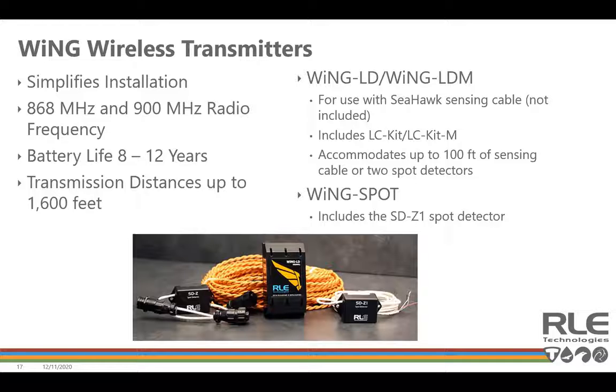The sensors themselves are compact, and they have a battery life of 8 to 12 years, so quite significant. It's a AA 3.6 volt lithium battery that is included with the sensor. Amazing transmission distances, up to 1,600 feet, 600 feet of that direct line of sight from the sensor to the WING Manager controller. And as I mentioned before, the leak detection sensor will accommodate up to 100 feet of sensing cable or 2 spot detectors, and the WING spot includes the LD sensor and the SDZ1 spot detector. So again, you've got some flexibility on what it is that you want to protect.